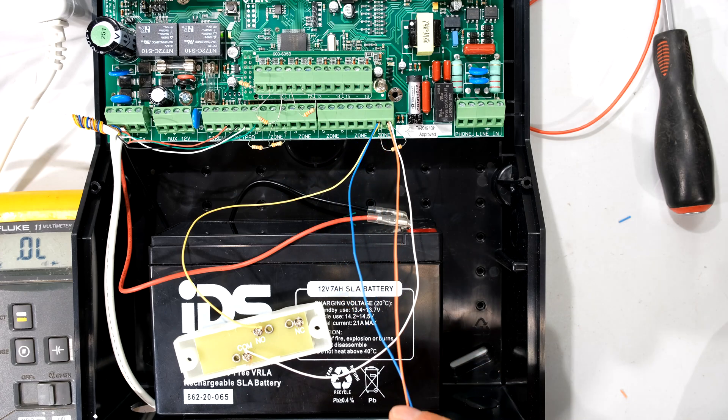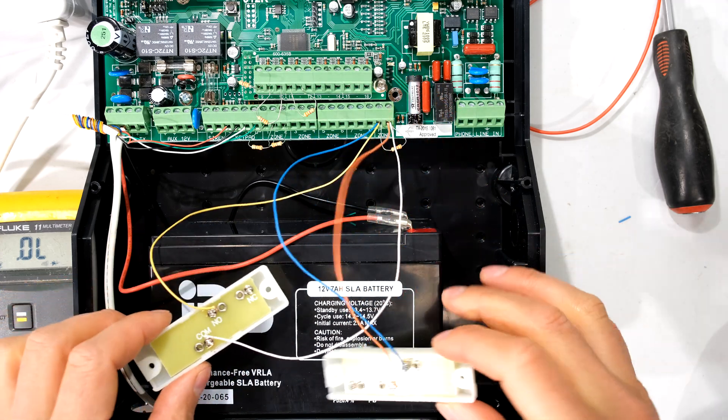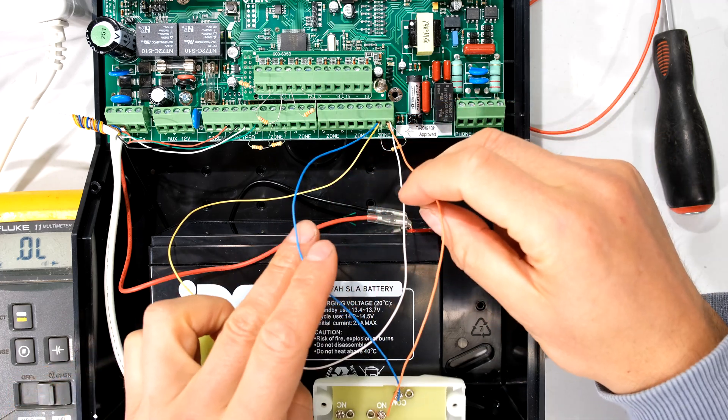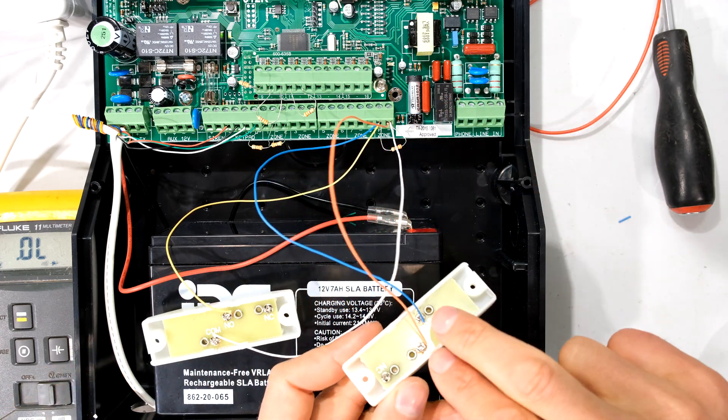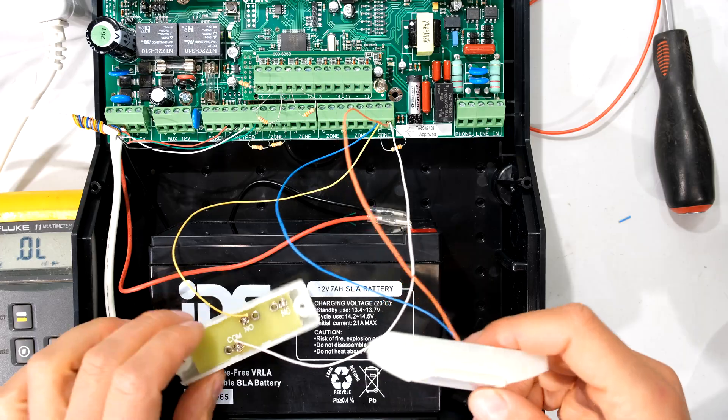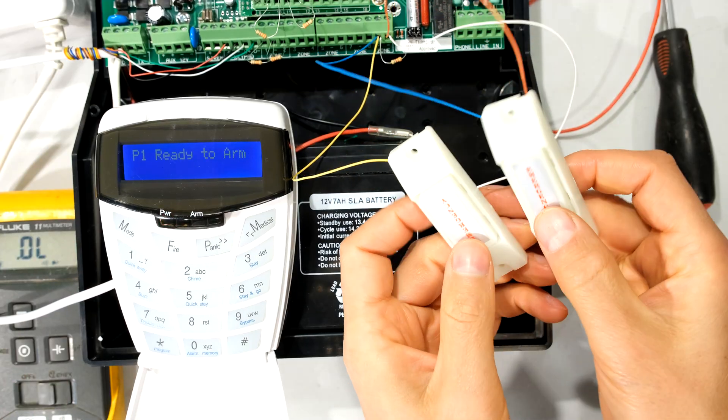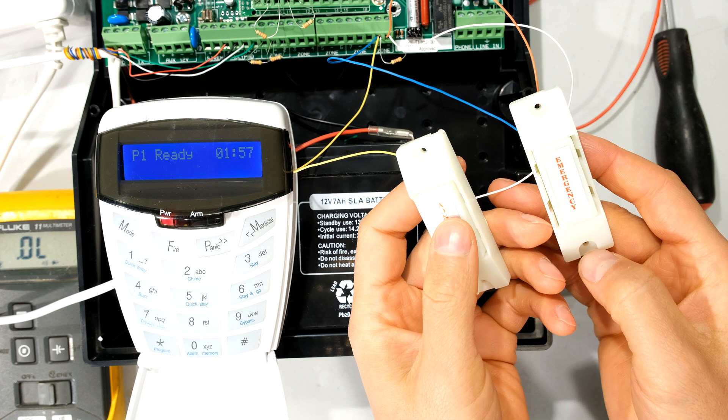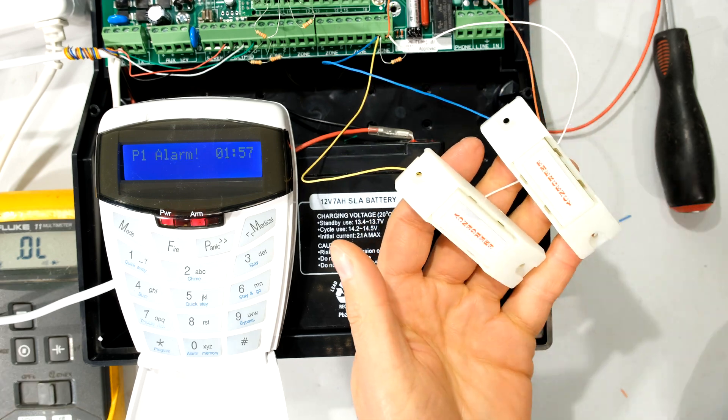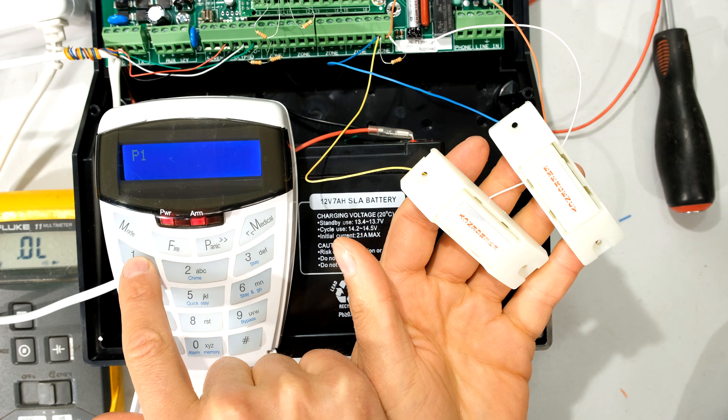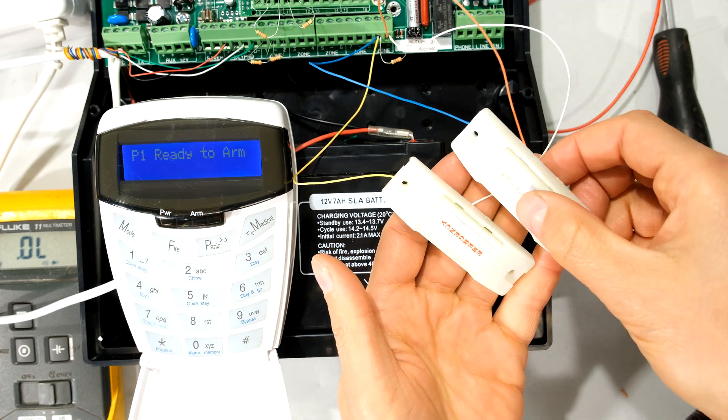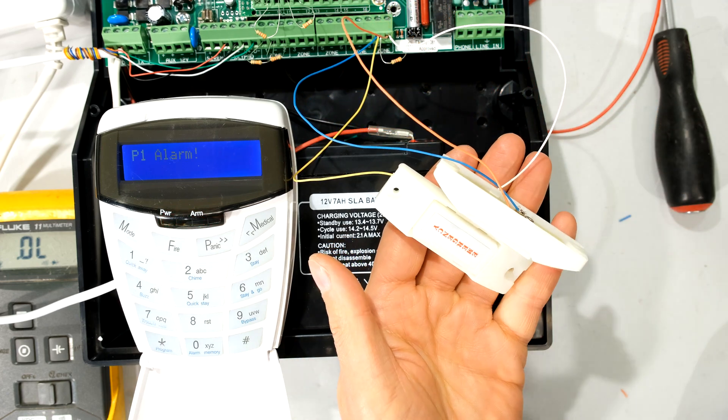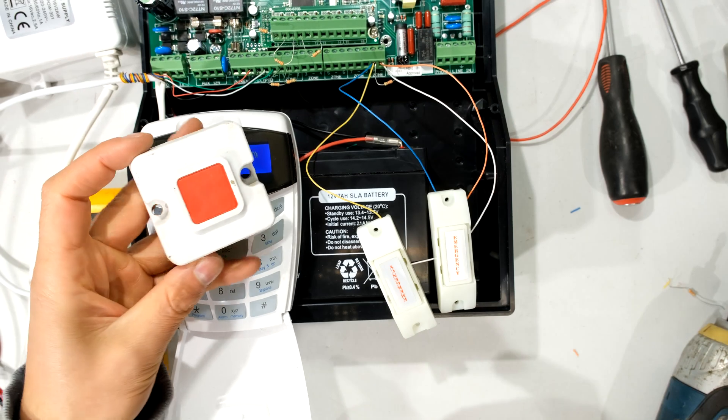So now you can see I've actually got two panic buttons wired to the panic terminal. As I said it doesn't matter about the polarity. These could be any way around. These are just switches. So if I press any one of these panic buttons I'll start with this one. Notice it says P1 alarm. I'll just reset it. And I'll press the other one. And there you can see panic alarm. So both are working.